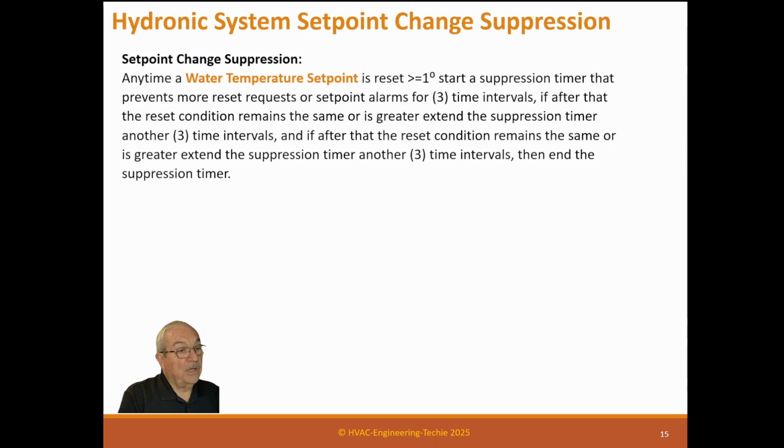So it'll drive your temperature request all the way to maximum, whatever that is, or minimum, whether your temperature's going up or going down. And that's not what we want to do. That would increase energy proportionally, so we're not doing that. Now, eventually the alarm will trigger. The operator will figure it's not working, but we don't want to drive these resets completely out of sight because of that. And it may not be that it's not working.